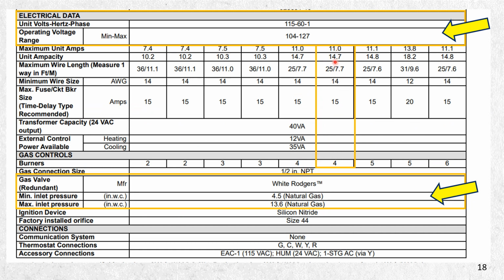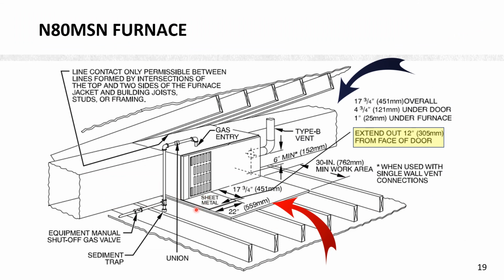Same thing here. Numbers are really close to the same. Just keep those in mind when you're looking at this. The other thing too, I've noticed when I go to these job sites and look at the install, no one puts a sheet metal cover under the furnace. What we do, which is fine, that's how we get through it, is they put an auxiliary drain pan. Just make sure your auxiliary drain pan encloses the whole entire furnace, in case you have flames shooting out here, you're protecting the wood flooring and the rafters from fire. But keep that in mind too. So always look at this stuff when you're installing, in the manual, to make sure.